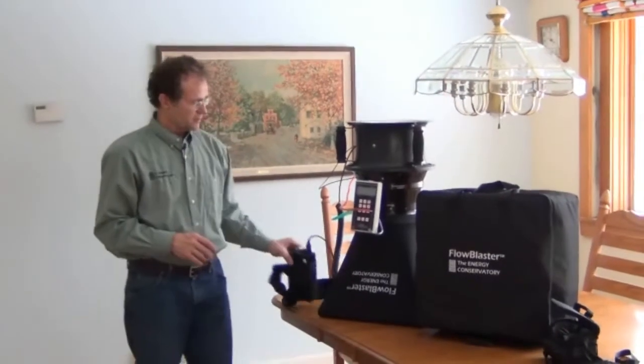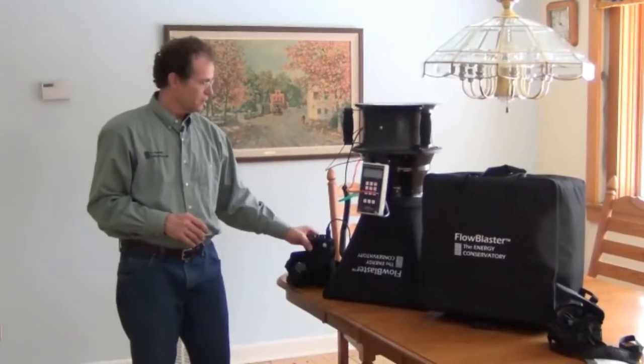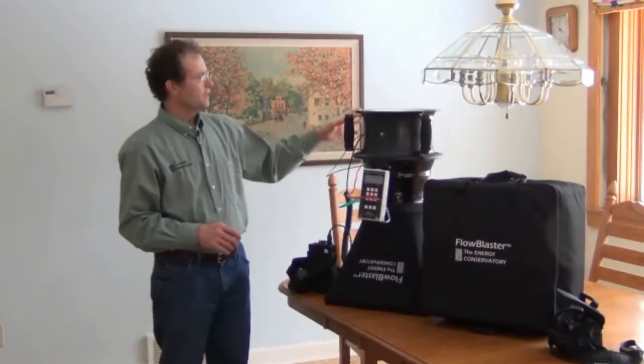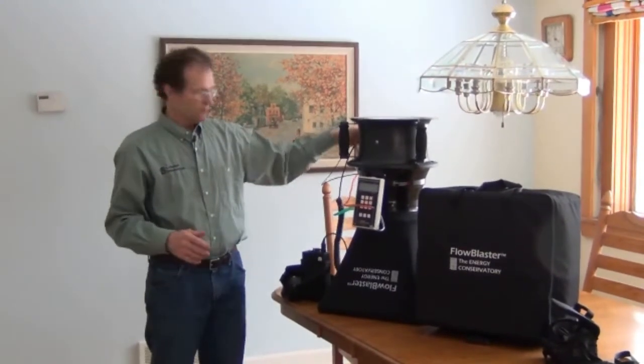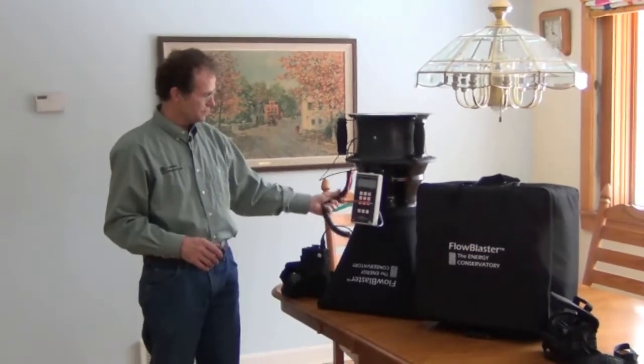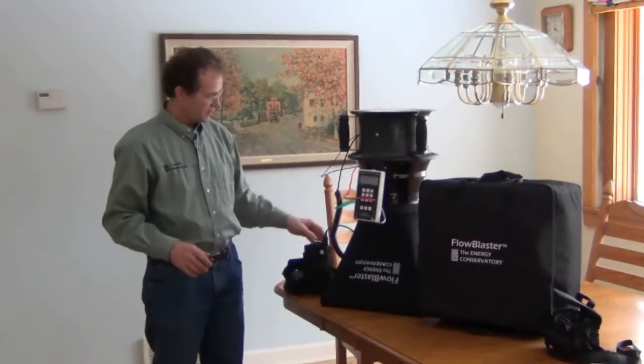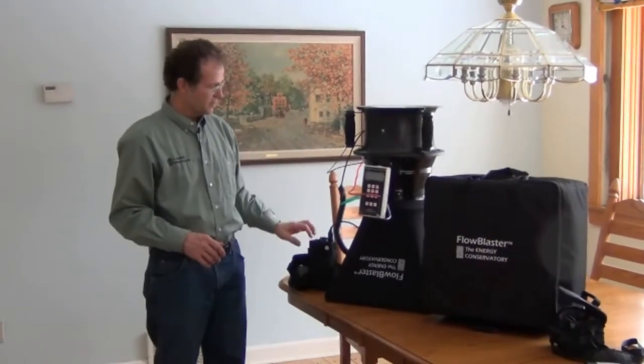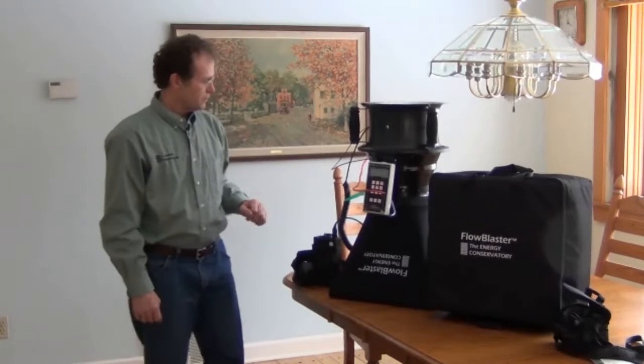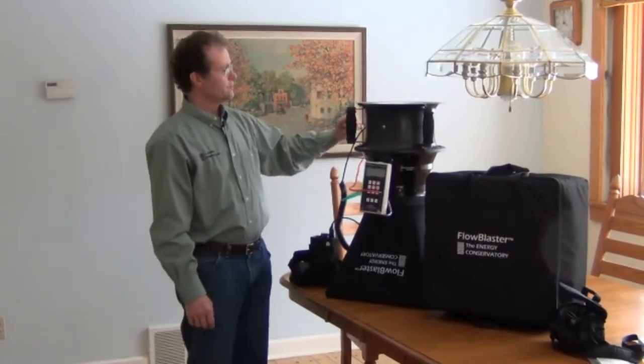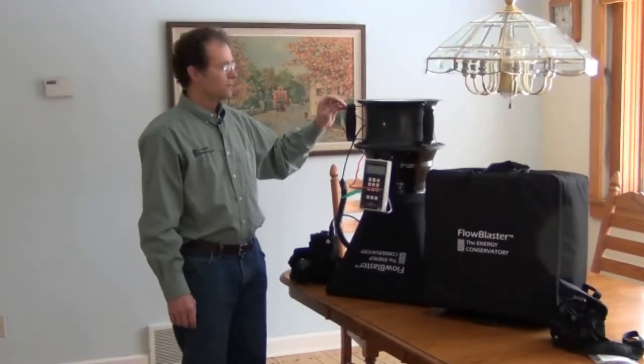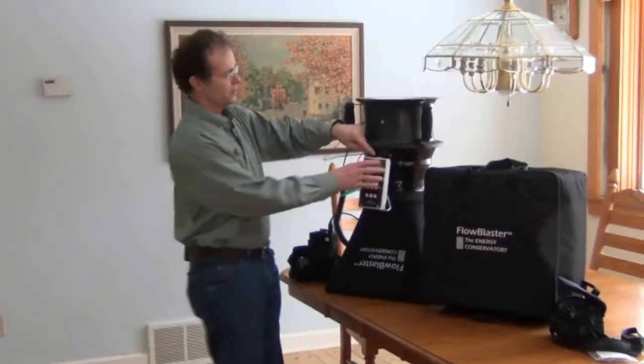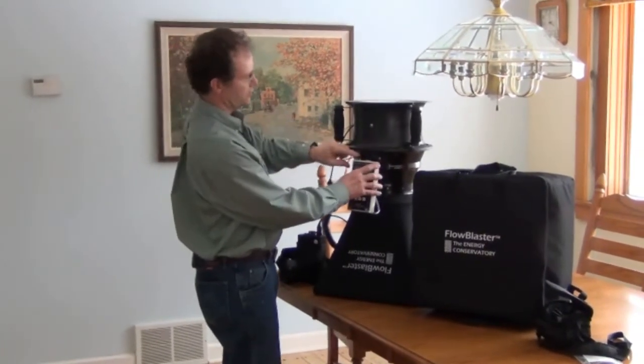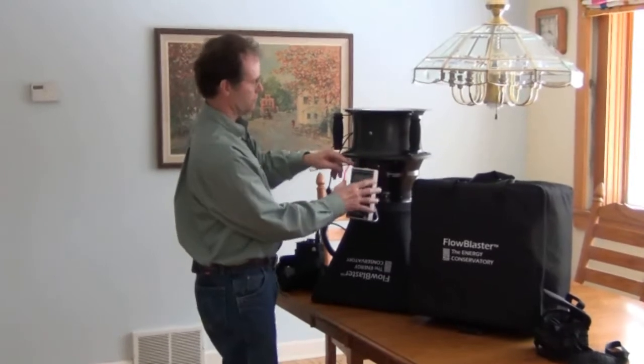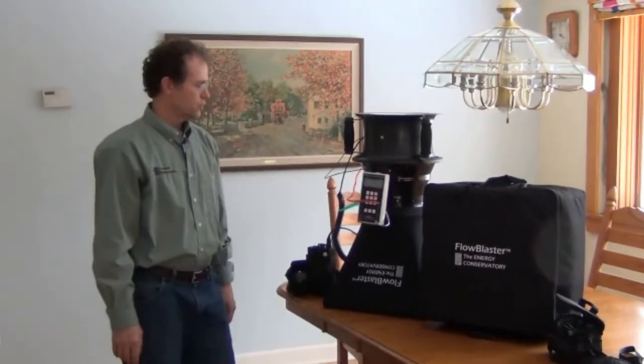Then we connected the battery-powered speed controller. And we connected that to the Duct Blaster fan with this coiled cord, and connected the coiled cord to the battery pack. And there's also a fan connect cable running from that same cord, and we plug that into the top of the DG700 like we do when we're using the cruise function of the gauge.